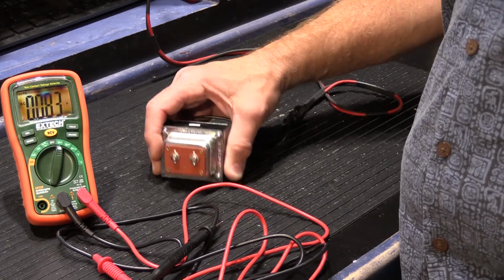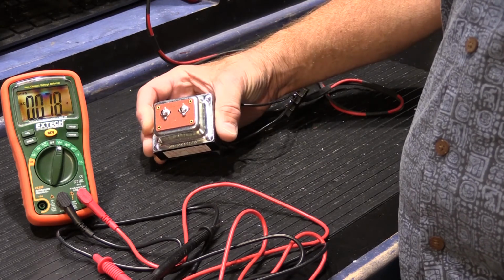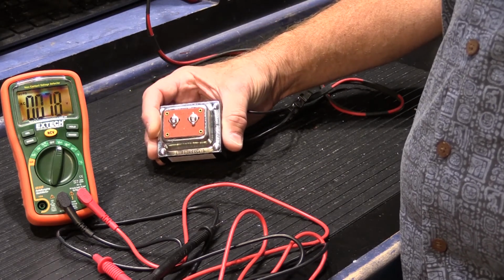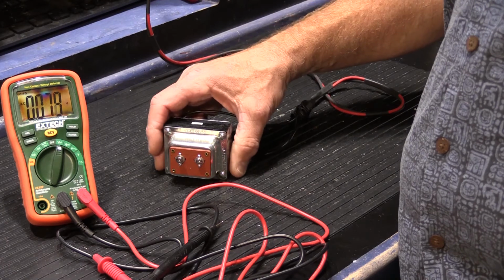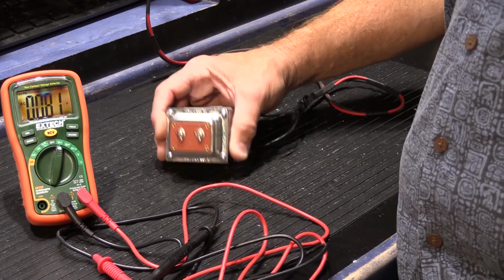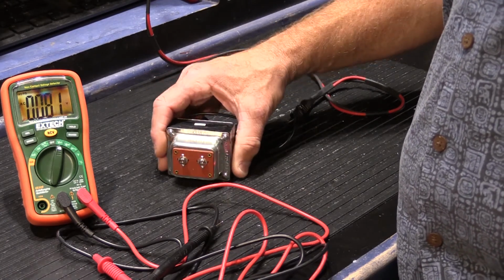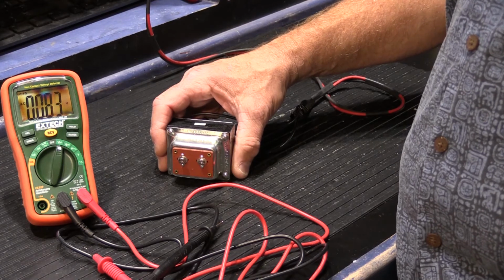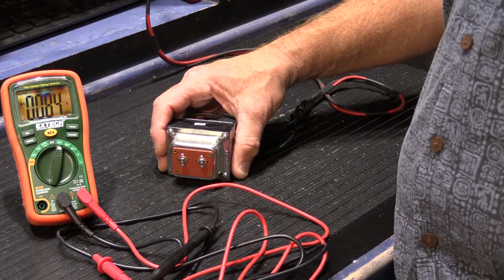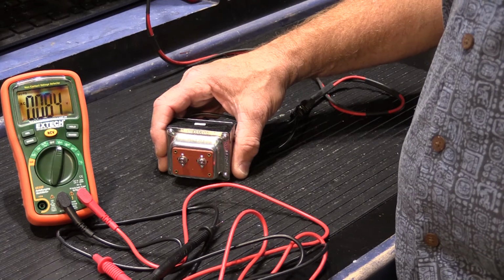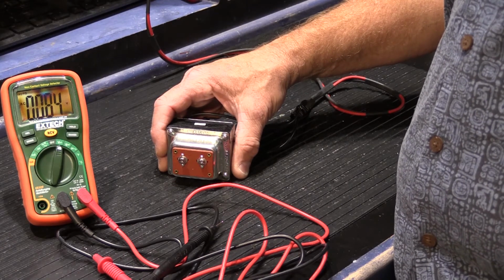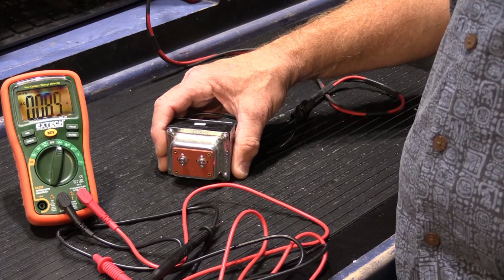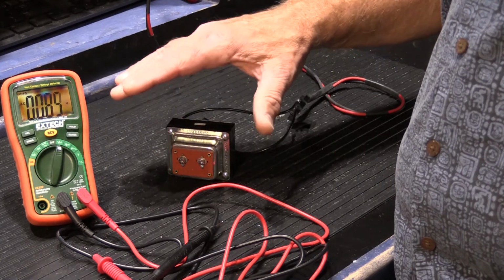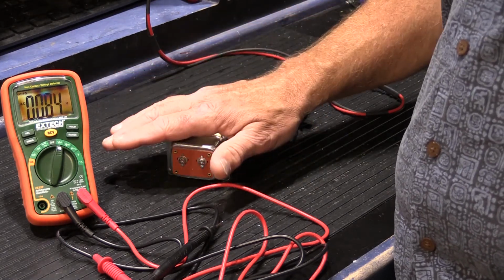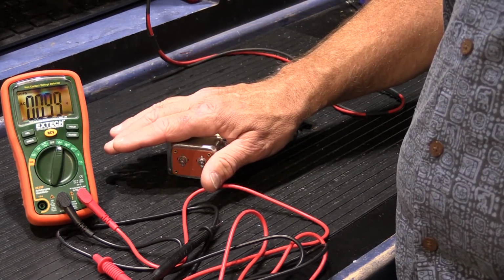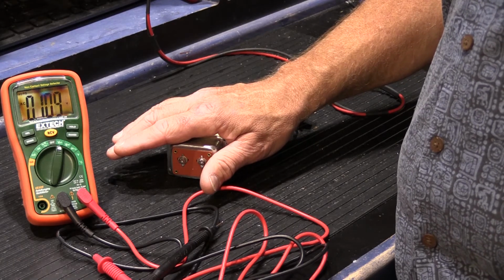A 16 volt transformer like this is rated to output 16 volts AC under full load, under its 30 watt capability. Right now this transformer is free running, nothing connected to it. So the voltage is higher, because when NuTone designed this transformer, they knew it would be installed in an intercom system demanding power from it, using up many of those 30 watts, which creates a drop in voltage.